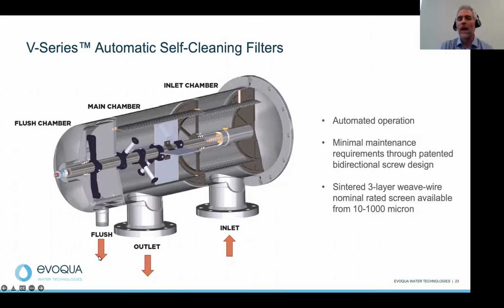So you're starting to flow out the flush line. But you have a rotation effect here. That rotation creates a rotational effect down the shaft, basically rotating the nozzles 360 degrees throughout the screen. But this shaft is actually connected to something called a bidirectional screw at the other end. That bidirectional screw, think of your fishing reel. As you're constantly rotating in one direction, you actually have the reel going back and forth. The same idea is occurring here. We're rotating always in one direction, and at the end of the linear motion, you go in the opposite direction. That allows all of these nozzles to effectively clean 100% of that surface area of that screen very efficiently, very controlled.